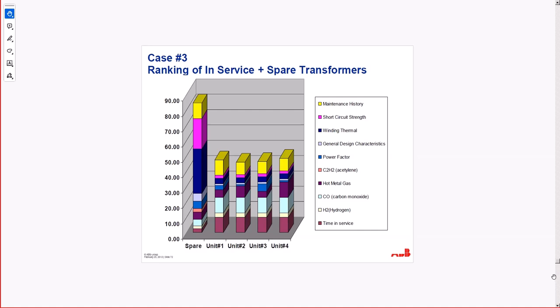You can see here maintenance, short circuit, winding thermal, general, power factor, acetylene, hot gases, carbon monoxide, hydrogen, and time in service. So those are the bullets that you put on top of each other, and then you see, for instance, unit 1, 2, 3, 4, where do you want to be, where you are with the life, because of this criteria that you apply. And then you have a spare transformer that is like new and has all those margins still available, but you burned a lot of that out already on the existing 4 units, right? So you have much less available.